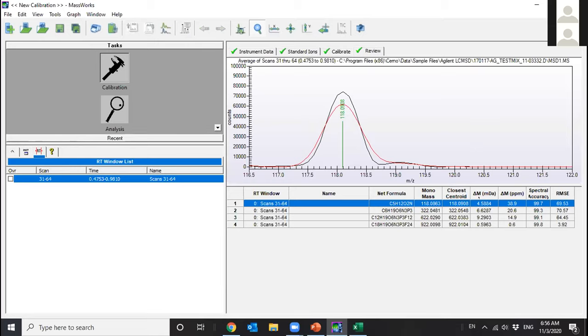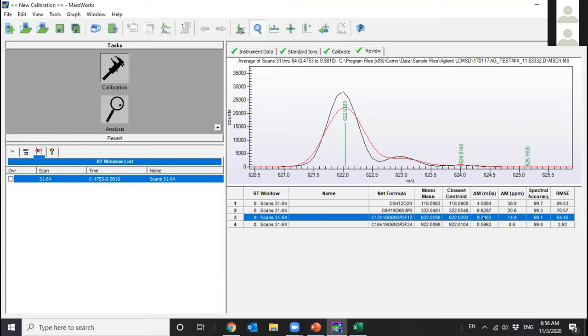For example, in this case, the delta M, the mass recovery, is somewhat high at 4.5, 6.6, and 9.2. And they all tend to be positive errors, a few millidaltons a little too high. That's typically an indication that the calibrated peak shape after calibration is too wide. And this is perhaps the only adjustment you need to make.